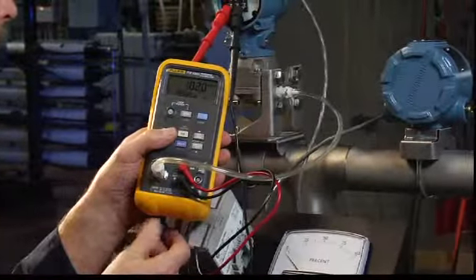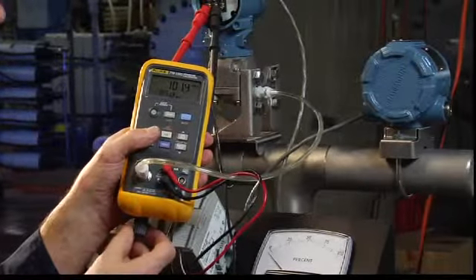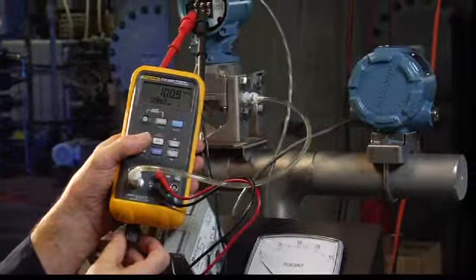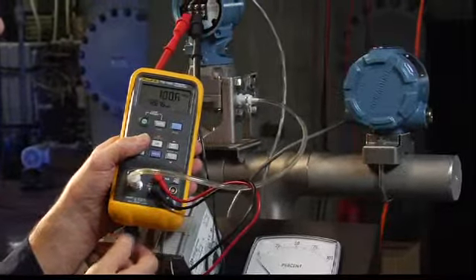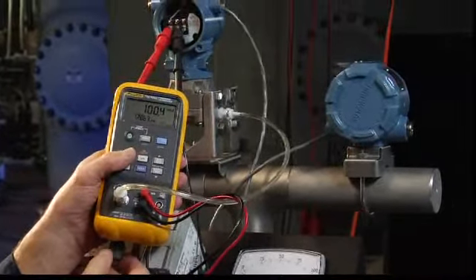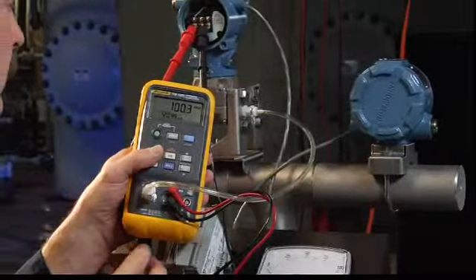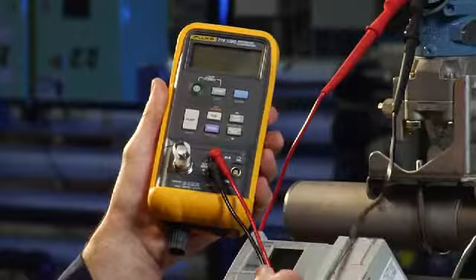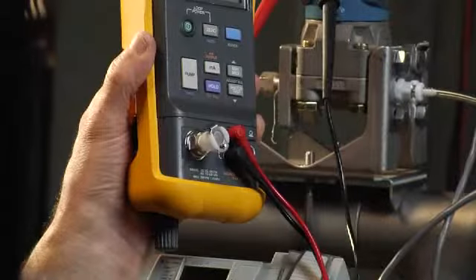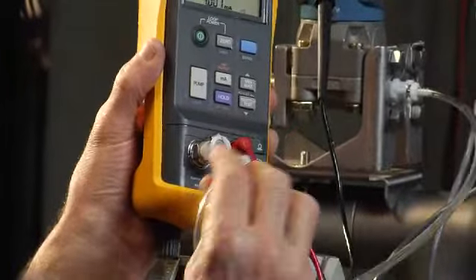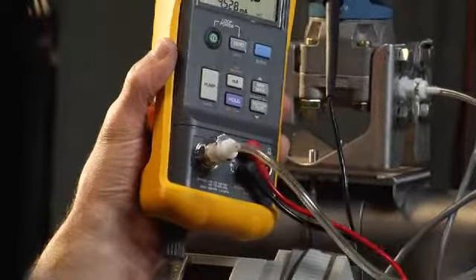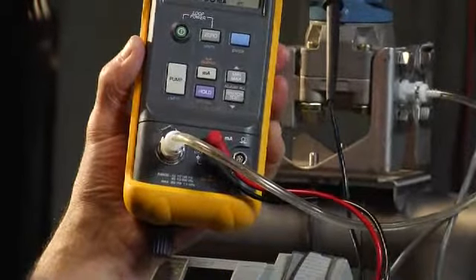In this demonstration, we're going to test the Rosemount 3051 pressure transmitter with an input range of 0 to 200 inches of water while verifying the milliamp output range of 4 to 20 milliamps. Connect the test leads from the output of the 719 to the power connections on the transmitter. Then, make a pneumatic connection between the input of the transmitter to the output of the 719.